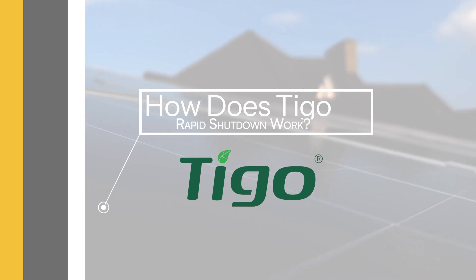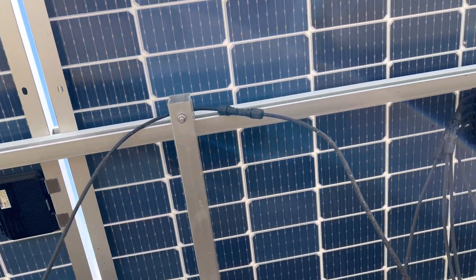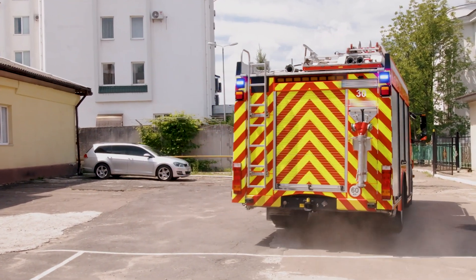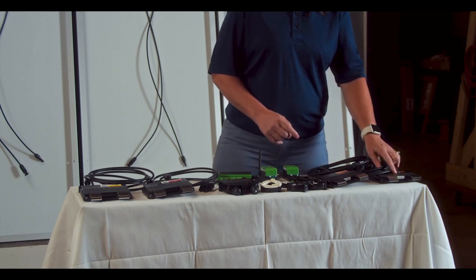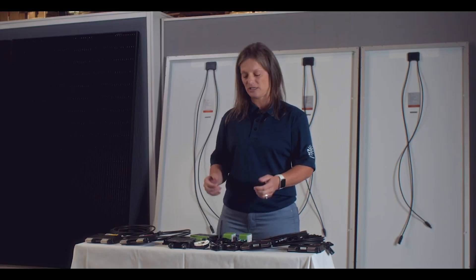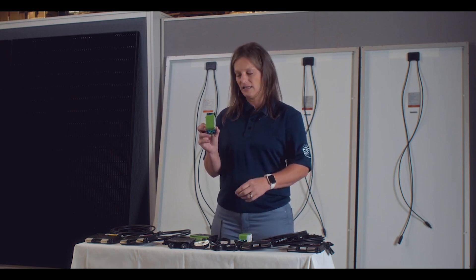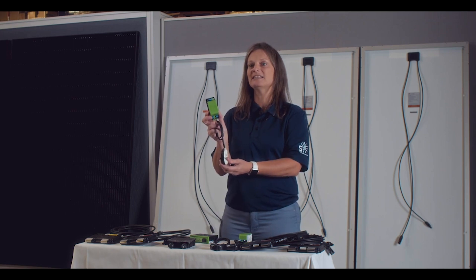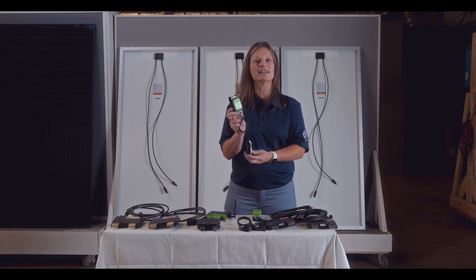How does Tigo rapid shutdown work? It's pretty simple. In the event of an emergency such as fire, the fire-rated Tigo rapid shutdown modules immediately cut off the flow of electricity from the solar panels, making the system safe for first responders. This is especially important because solar panels can generate high voltages even when the grid goes down. Both the F and the 2F units use PLC, or power line communication, via the RSS transmitter to meet certification requirements. The RSS transmitter emits a keep-alive signal until a shutdown has been initiated. Once the shutdown is initiated, this kills the keep-alive signal, shutting down the TS-4, reducing each PV module's voltage to six-tenths of a volt in less than 30 seconds.